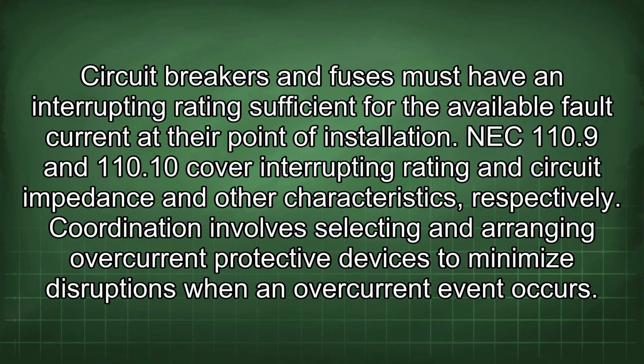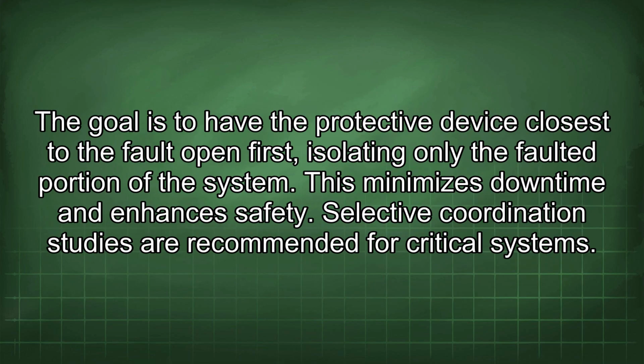Coordination involves selecting and arranging overcurrent protective devices to minimize disruptions when an overcurrent event occurs. The goal is to have the protective device closest to the fault open first, isolating only the faulted portion of the system. This minimizes downtime and enhances safety. Selective coordination studies are recommended for critical systems.